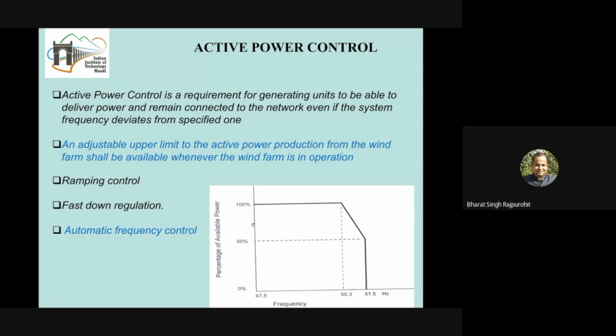Fine. Then there is fast down regulation. What is the meaning of fast down regulation? When a wind farm is operating and suddenly, due to higher power generation being available and the frequency going above the limit, the wind farm is expected to reduce its power output. How fast they will be able to do this is the fast down regulation limit. I will give you data for all these regulations, on what is actually demanded by the grid in Indian conditions.